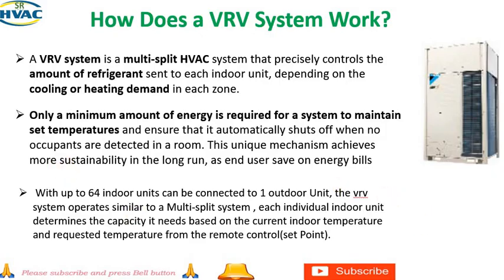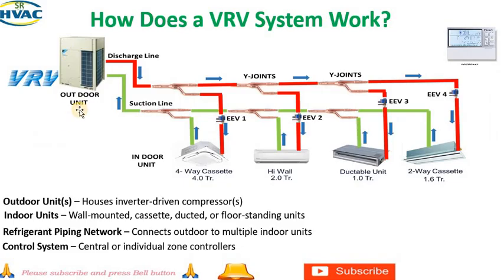Next, we will see the flow diagram of the Daikin VRV system. This is the outdoor unit. The piping is done with the help of joints, or branch. This is the branch, and this is our suction line. These are the major units that are used in designing the VRV system. The first is our outdoor unit. These house the compressor, the inverter compressor. This is the outdoor unit.